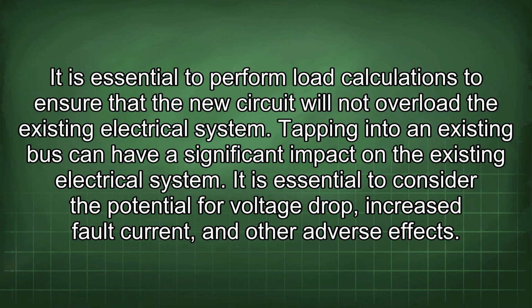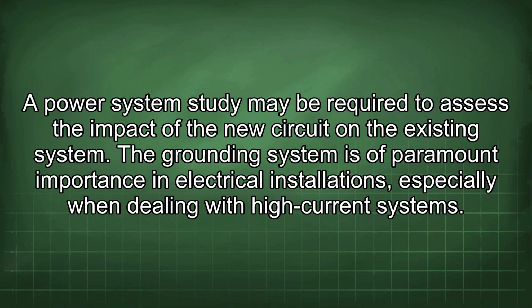Tapping into an existing bus can have a significant impact on the existing electrical system. It is essential to consider the potential for voltage drop, increased fault current, and other adverse effects. A power system study may be required to assess the impact of the new circuit on the existing system.